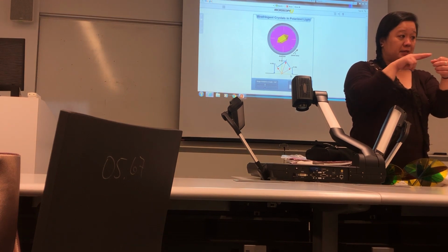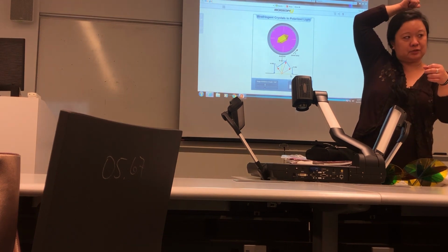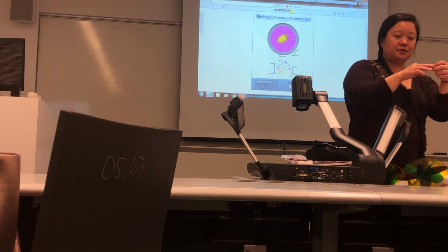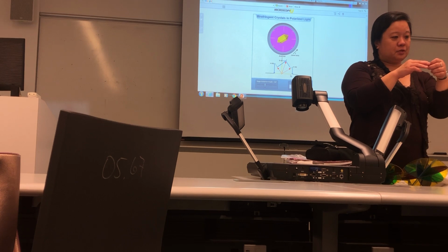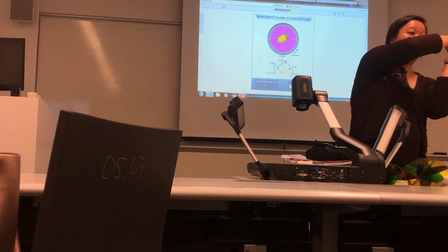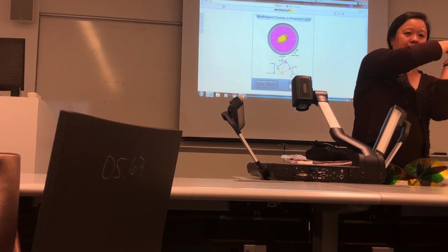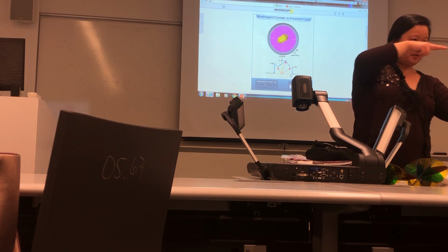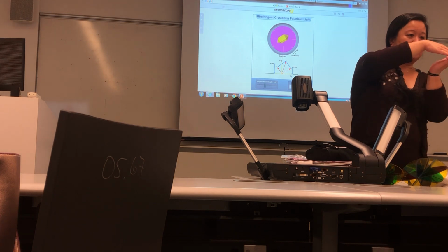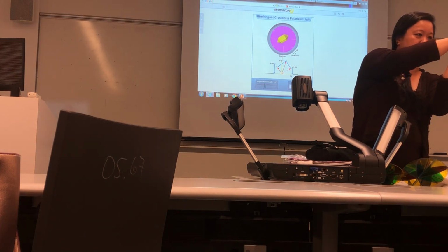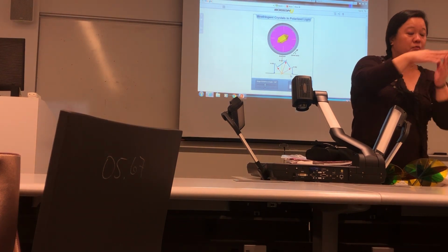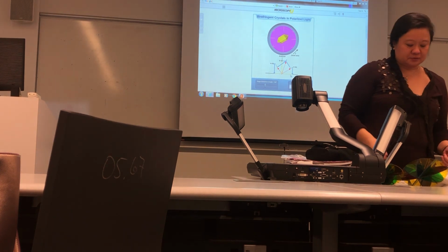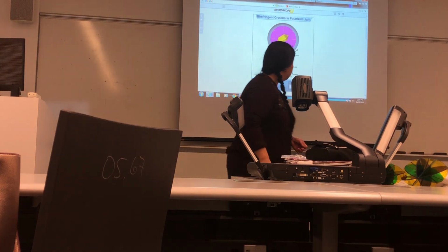You've got the first order red compensator, which will make things look like that in the background. You've got your quarter wave compensator, and you've got your quartz wedge, which is literally a wedge of quartz, so it is what it sounds like. As you insert it into the compensator slot of the microscope, the amount of quartz is thicker and thicker because it's a wedge. And what you'll also see is that it'll have an effect on the interference colors that you're observing.